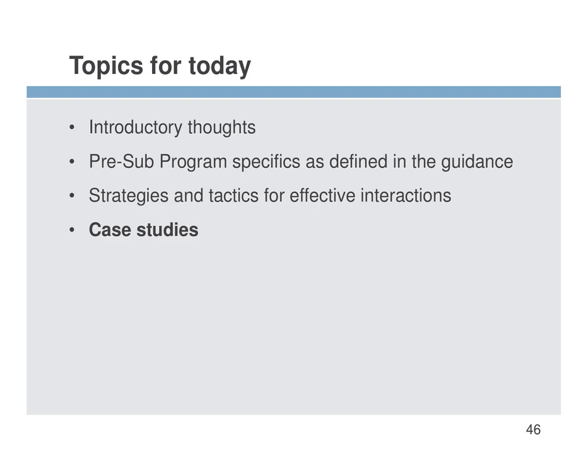When it says see previous slide, I meant the slide 2 back, or 3 back, that says, do you agree with our test matrix? So I apologize for that. But if you're looking for an idea of what a test matrix would look like, let me think out loud about this because I've done numerous of these but don't have it written down. So this may be a multi-page document, and your first column in your table is going to say something like either risk to be addressed or design input to be addressed.